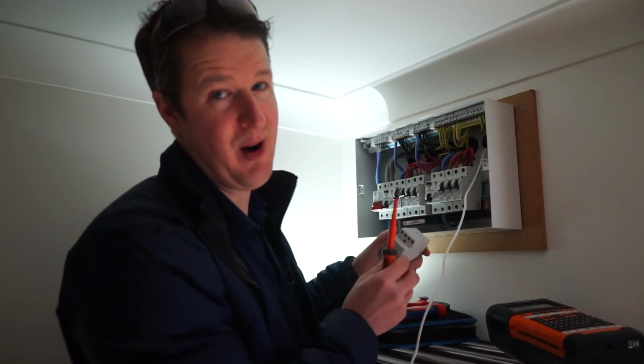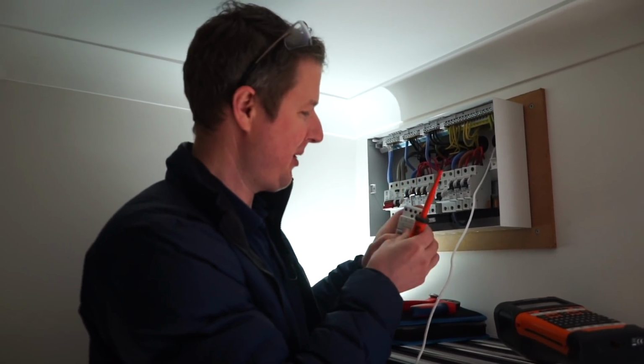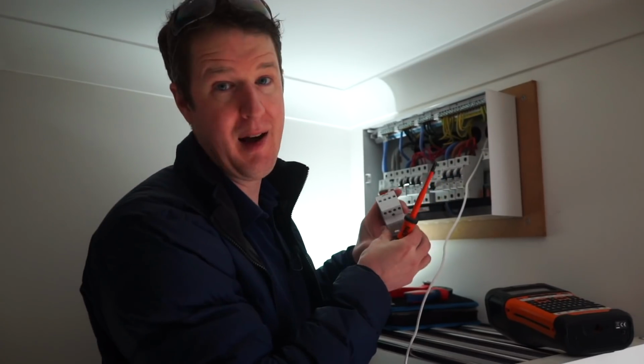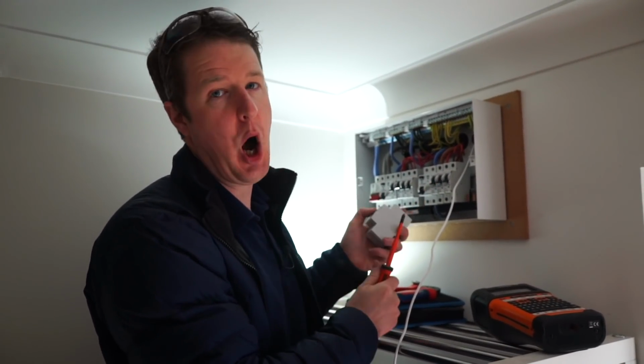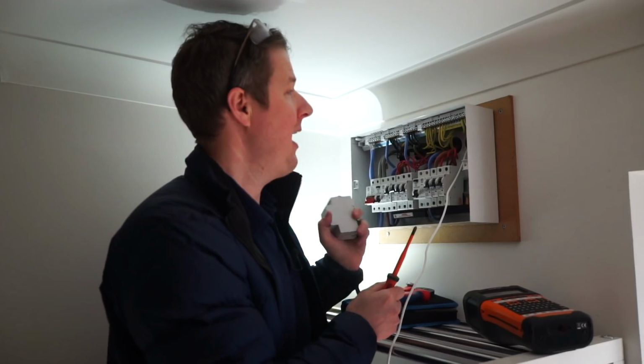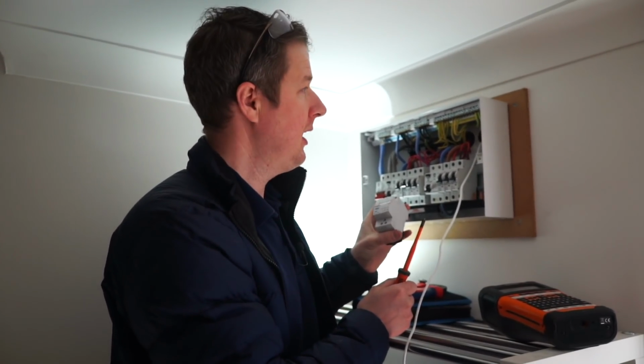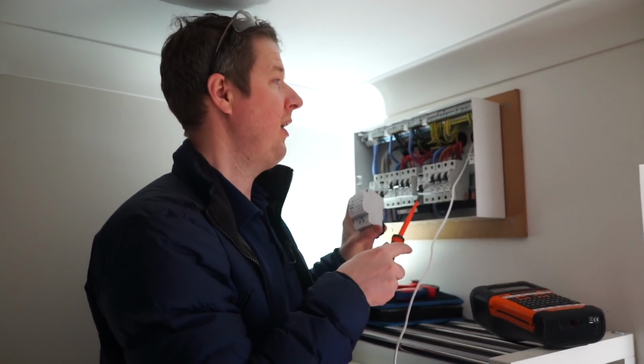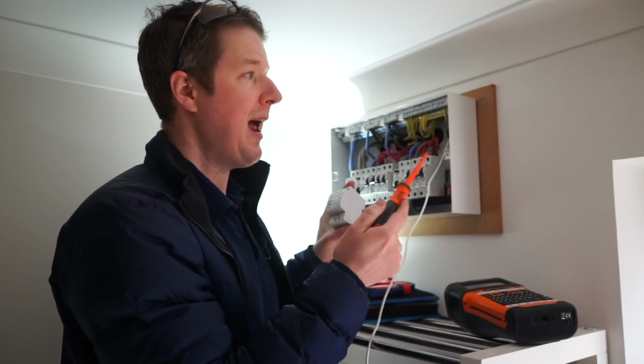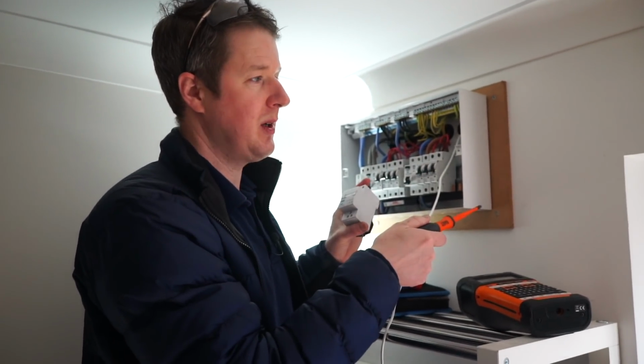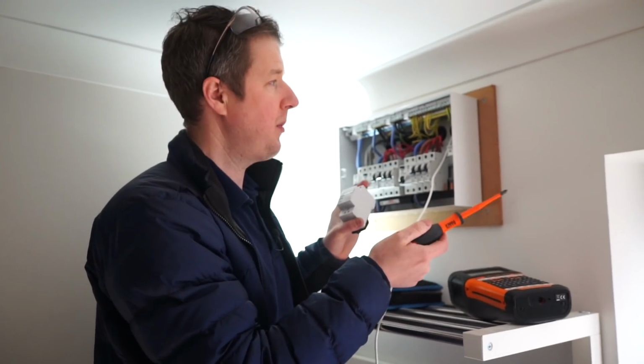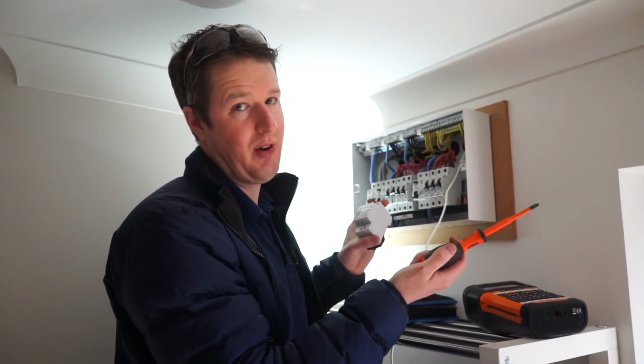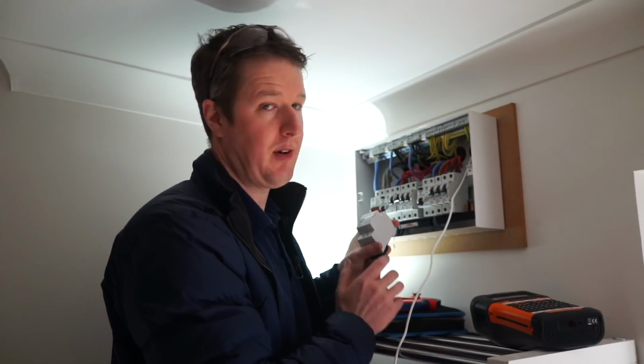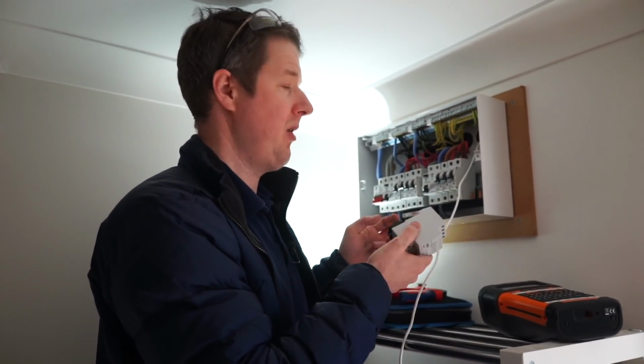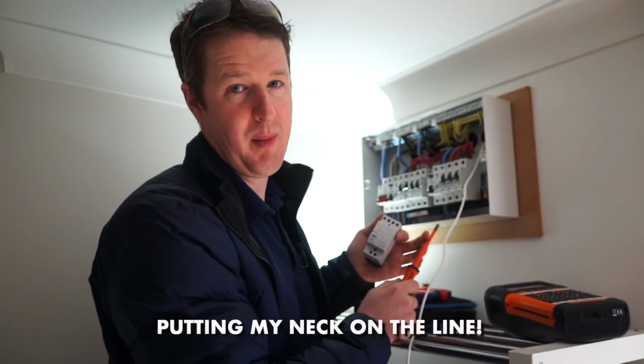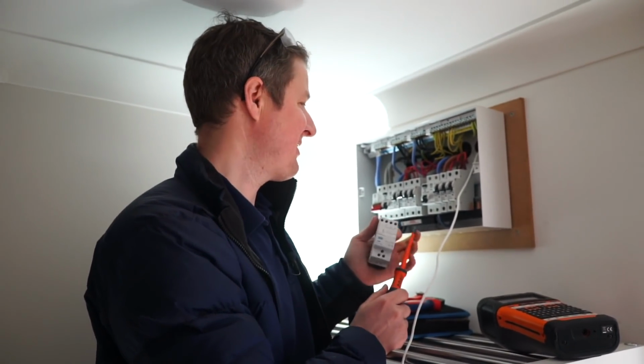But let me know if you think I'm wrong in the comments - I know some of you probably will, and I always like to hear your reasoning about things. At the end of the day, we've got to make our own engineering judgment about stuff like this. For me, the aesthetic disadvantage of putting in an extra enclosure - which technically I'd have to make a BG enclosure, and it would look awful, the customer wouldn't be happy with it - that's a bigger downside than the technical disadvantage of putting a BG transformer in an MK consumer unit. But there we go, I'm putting my neck on the line there, probably going to get slaughtered in the comments.